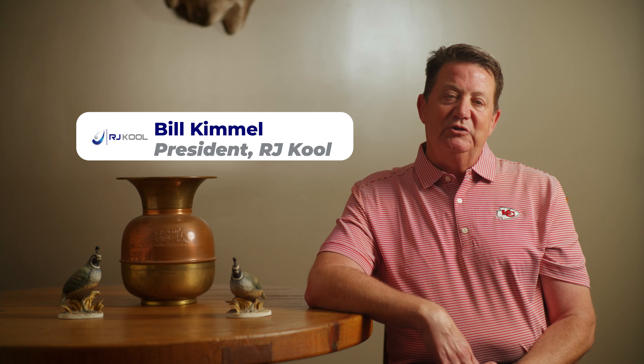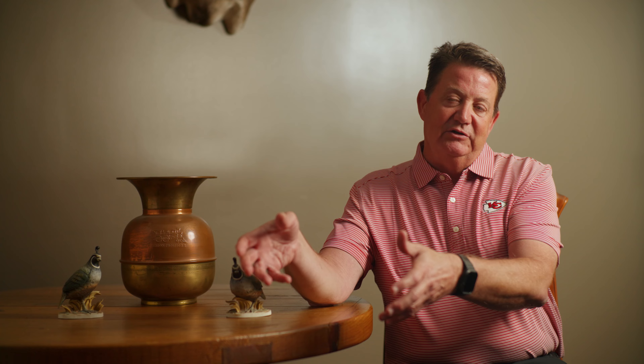You want to be able to pull a full load out of the washer and transfer that directly to the dryer. One thing that drives me insanely crazy about our industry is that we never started sizing correctly. If I bought a 50-pound washer, I should need a 50-pound dryer — that would make sense. But we say 50-pound washer and a 75-pound dryer. It's based on volume — how many pounds per hour you can dry versus wash. The math we use: take the size of the washer and multiply it by 1.5 — that should get you pretty close to what size dryer you need.